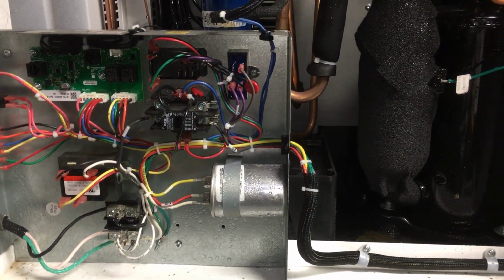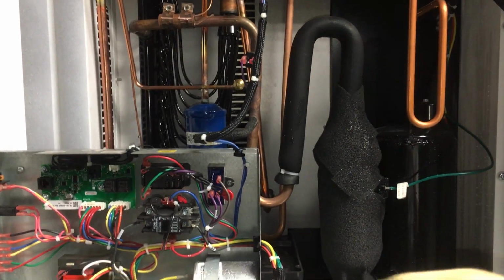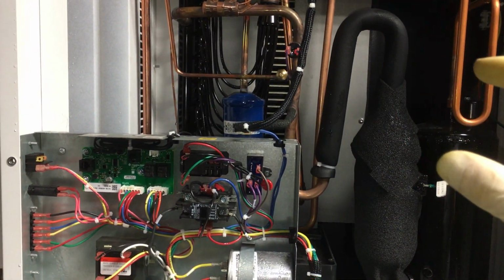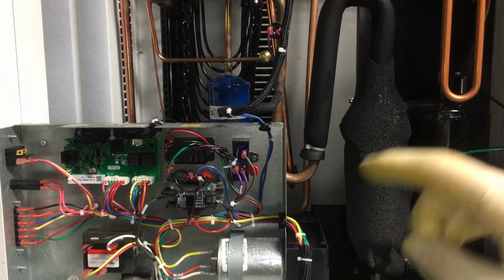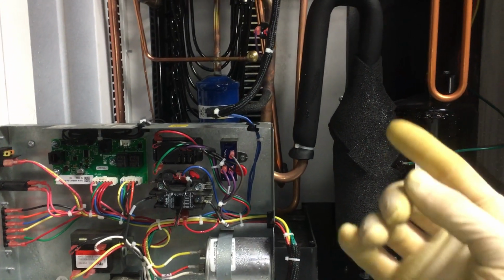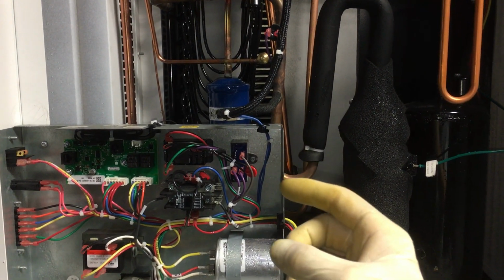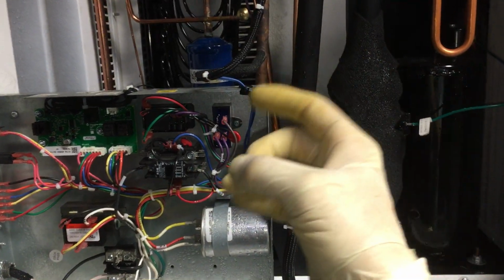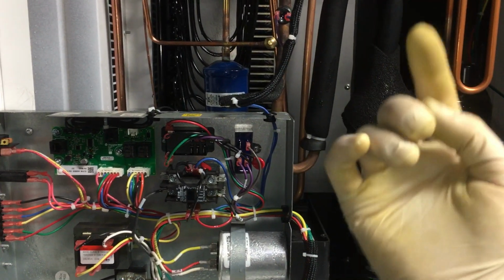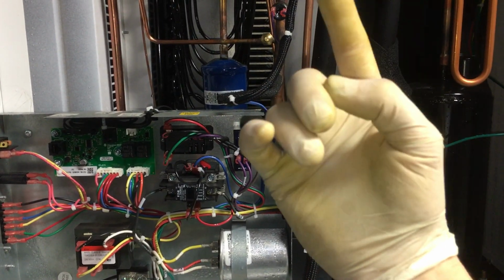The next rooms are going to be designed differently, so they can, and actually I might eliminate these, and I'm going to put a hydro reheat heat recovery kit with the LG system, where I take the third pipe waste gas that normally would be hot air, hot energy. The heat removed from the room by the process would go up to the roof on the condenser and be ejected as hot heat into the atmosphere.